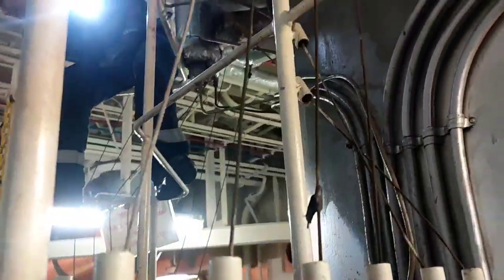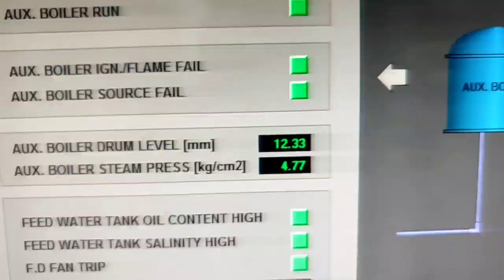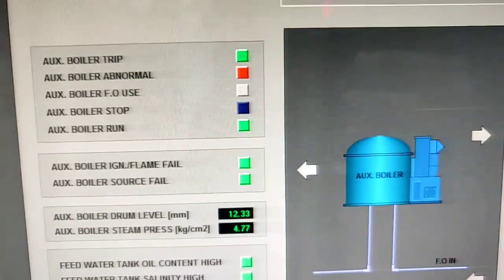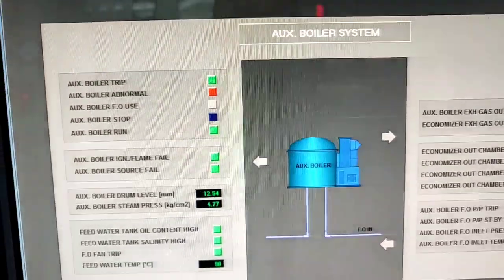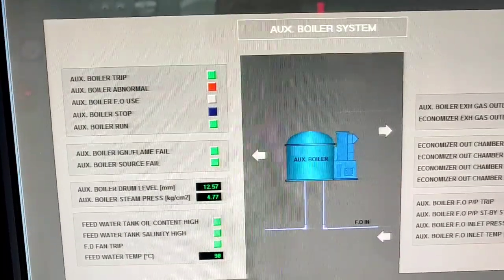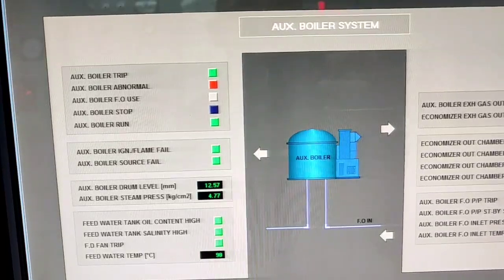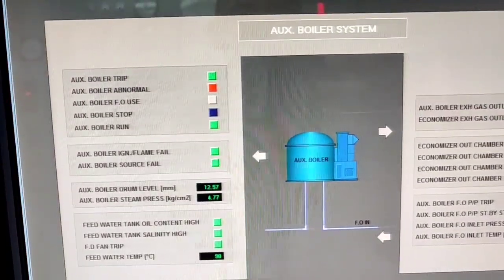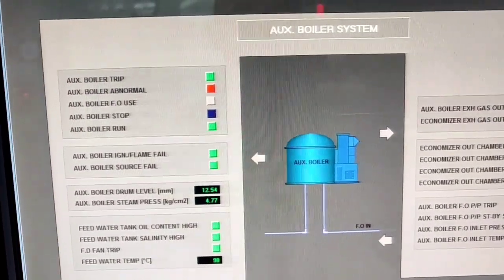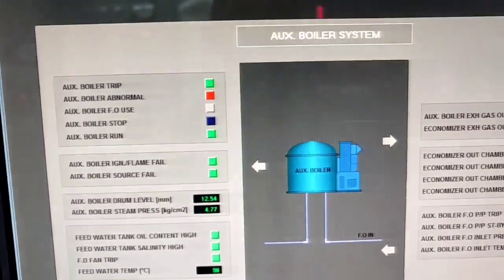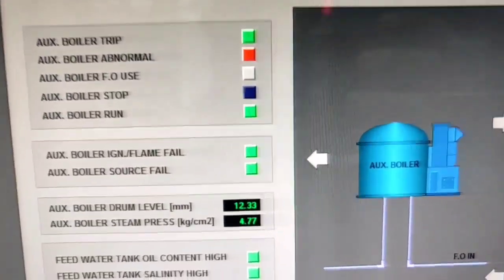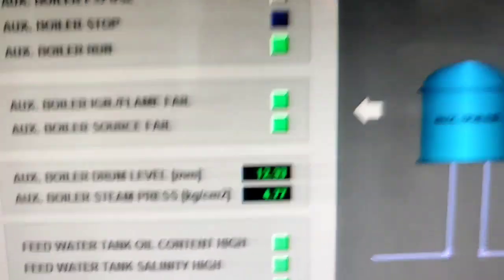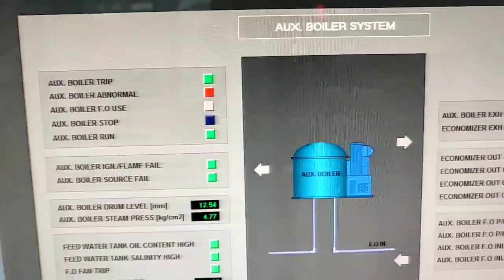As you can see, the level monitor and display on your auxiliary drum is now stable. The auxiliary boiler drum level reads 12.54 mm, or 30%, and it is stable.